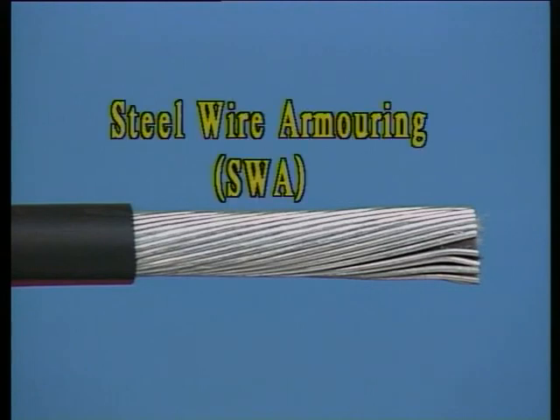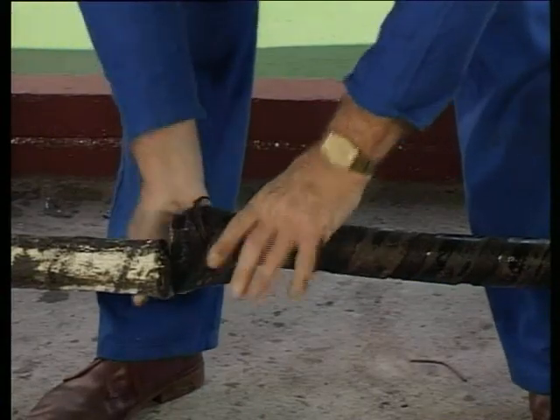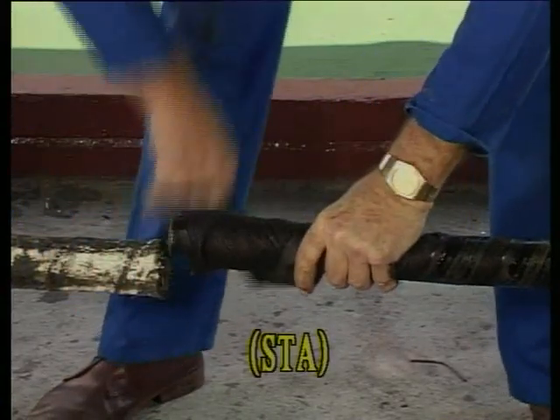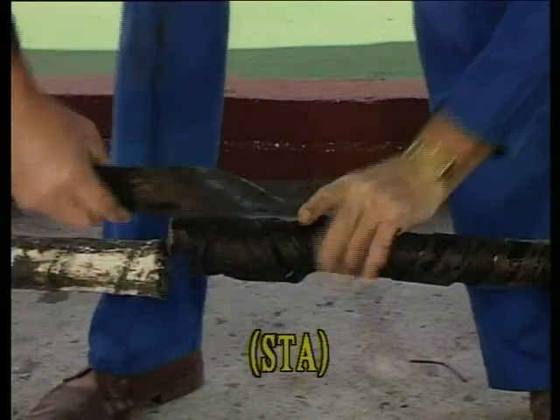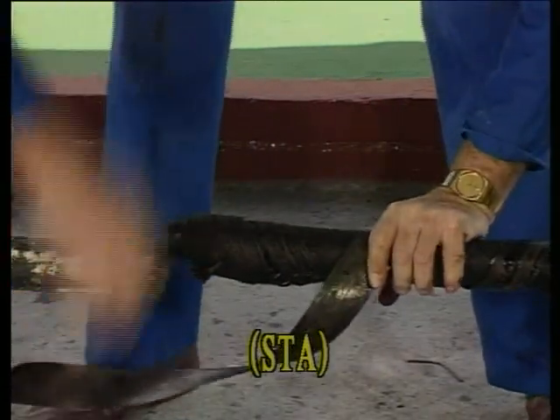Such an armoring type is referred to as steel wire armoring, or SWA, and is used mostly with PVC or XLPE insulated cables. Steel tape armoring, or STA, is another typical type, mostly encountered with paper insulated cables.